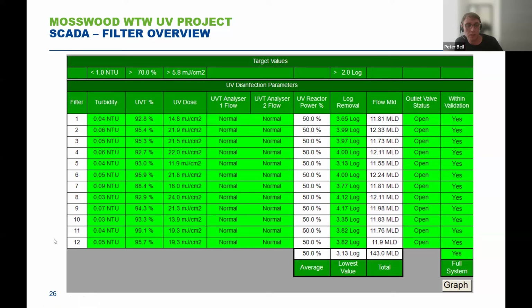UV transmittivity is another key parameter. If it is less than 70%, we can't target all of the areas that we need to target. The transmittivity won't allow that UV light to pass through and target all of that cryptosporidium. So that was another key parameter that we tracked. The UV dose shows that we are meeting the minimum dose. As we touched on earlier, we need quite a small dose of 5.8 millijoules per centimeter squared. When we run at 50%, we're achieving well above that, so it goes to show that we've got the right amount of dose there. The analyzers for measuring UVT need to have a representative sample, so we monitored the flow status to that. We then went on to show the power, log removal, and the flow through the filter as well, and if the valve is open.